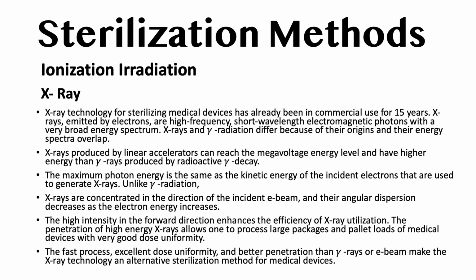X-ray technology for sterilizing medical devices has already been in commercial use for 15 years. X-rays are emitted by electrons and are high frequency, short wavelength electromagnetic photons with a very broad energy spectrum. X-rays and gamma rays differ because of their origin, and their energy spectra overlap.